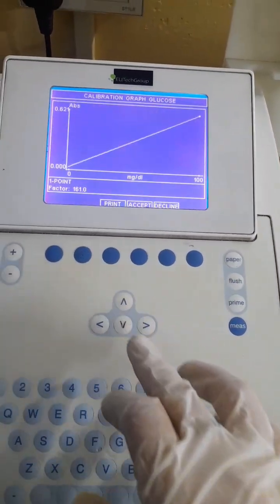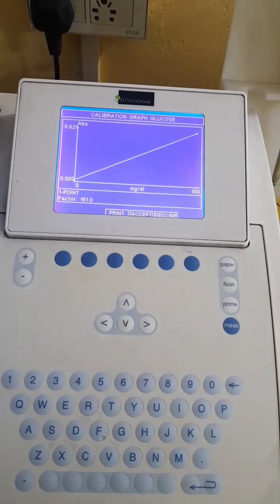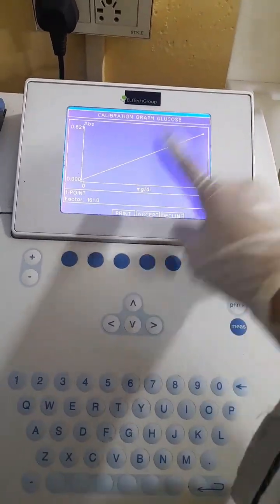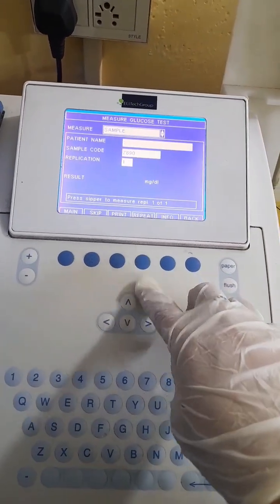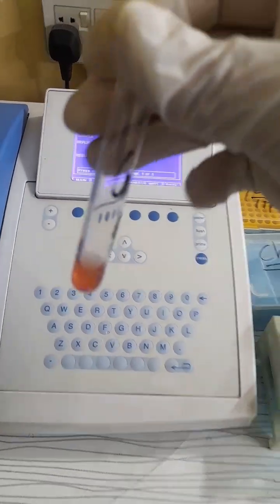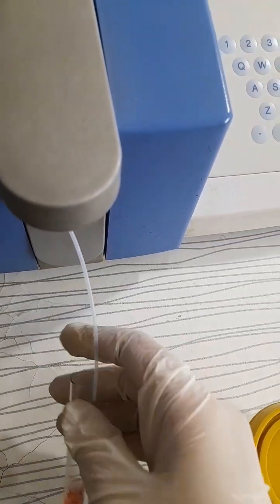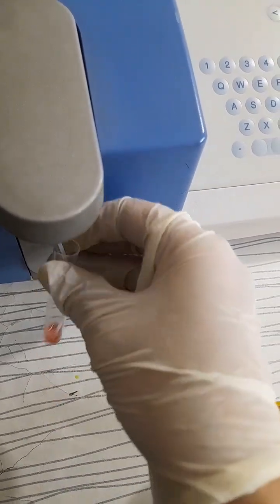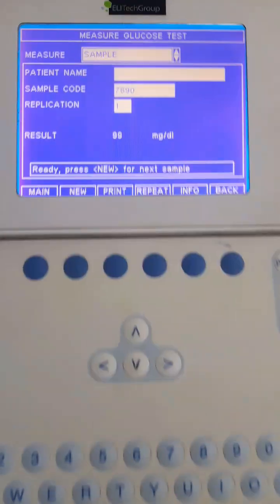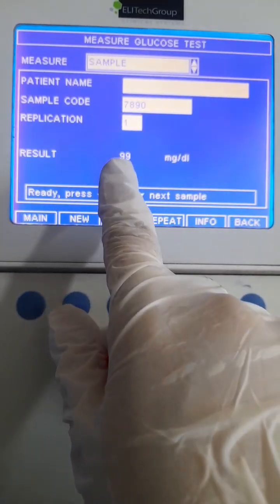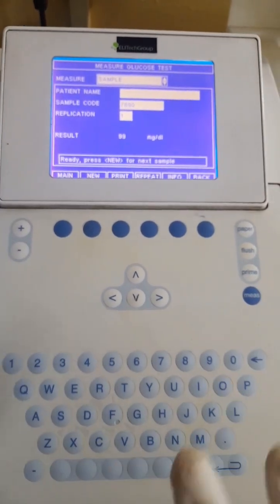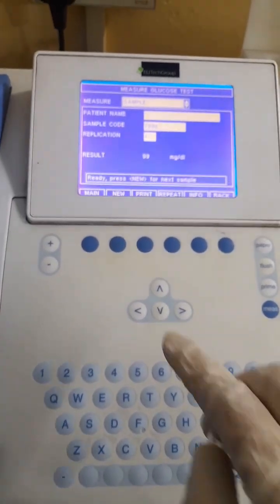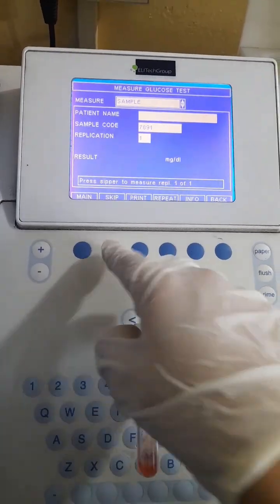This is the graph of calibration, which starts from 0 to 100 milligram per deciliter, which are the units. Now I am going to accept it. Now moving towards the standard, which is run as a sample to check whether my calibration is correctly done or not. Now let's see. You can see this is the concentration of 100 milligram per deciliter, and my result is 99, which is in the acceptable range. Ideally you have 100 milligram per deciliter, but this is acceptable. It means that my calibration is done properly, and now the results will be accurate.